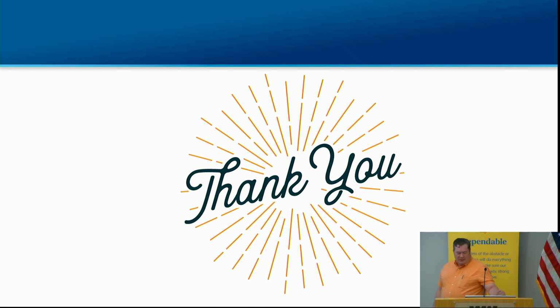Couple other major things, 210.52, you get into islands, peninsulas, kitchen countertops. Major change, we can't put receptacles on the sides of those cabinets anymore. We've done that for years, right? Put receptacles on the sides of these cabinets, especially islands, right? That's where we see it big time. We can't do that anymore. That's gonna be obsolete. You gotta have your receptacles either in, on, or above.